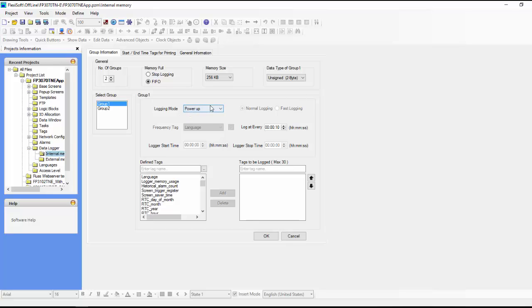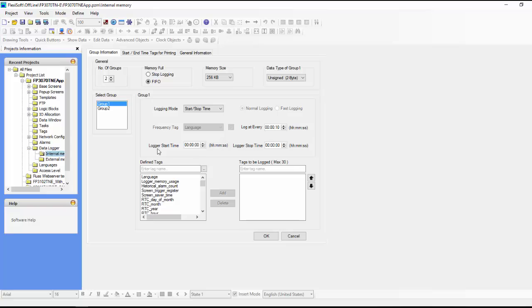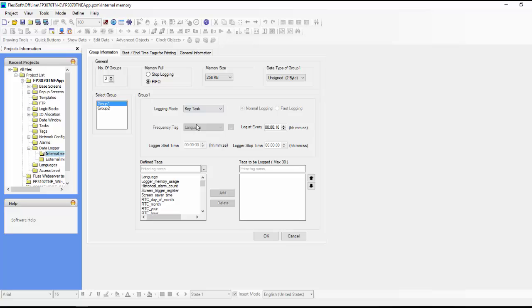The logging mode here, there's different modes. So you can say create a log when the system powers on and it just creates one log. You can have start stop time where you can set time every day of when you're going to log. And you can have a key task, so if the operator presses a key on the screen, then it will just create a log at that point.